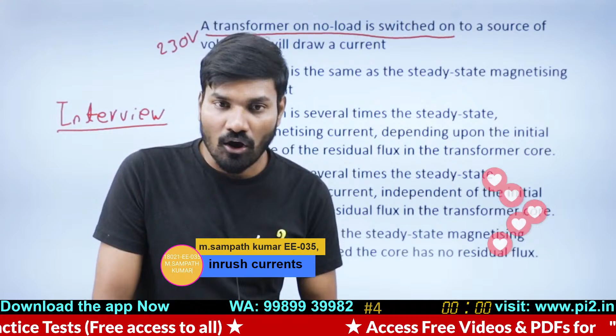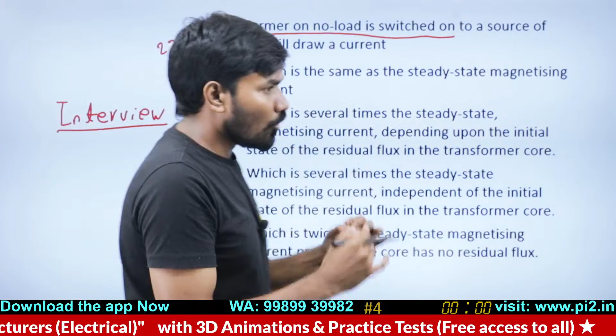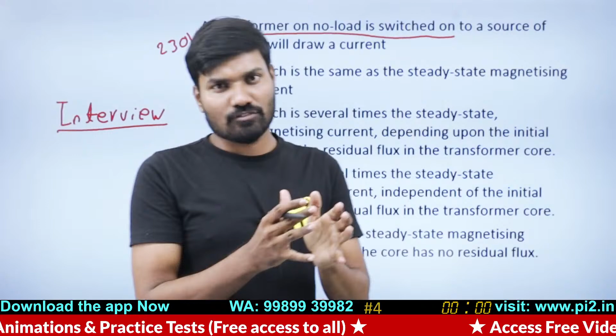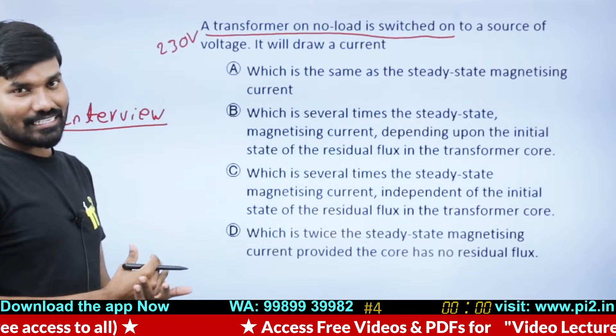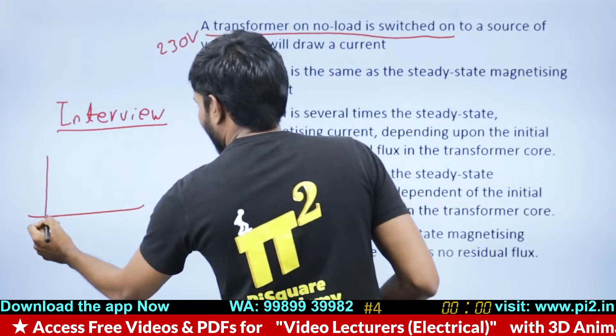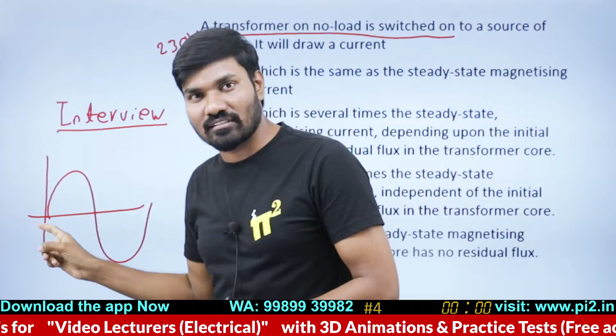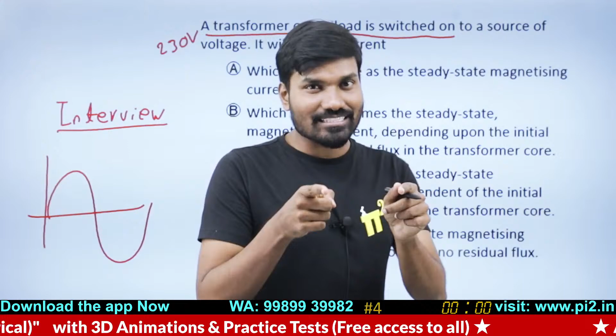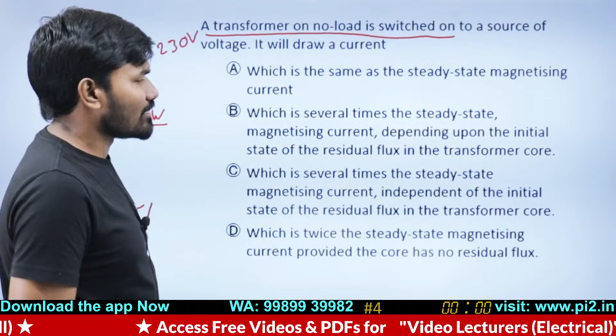Or you can call it flux doubling effect. Flux doubling effect or inrush current, they are related. You cannot really say what kind of current it will draw, whether it will be low or high. It is subjected to the condition of the transformer, more precisely, what residual flux it has at what instant of the voltage. 230 volts is not constant, right? It's a nice sinusoid. At what instant of this voltage you're closing the switch, and what residual flux it is having, based on these aspects that current will depend. So it's not same as regular current, which is several times the steady state magnetizing current, depending on the initial state of the residual flux in the core.